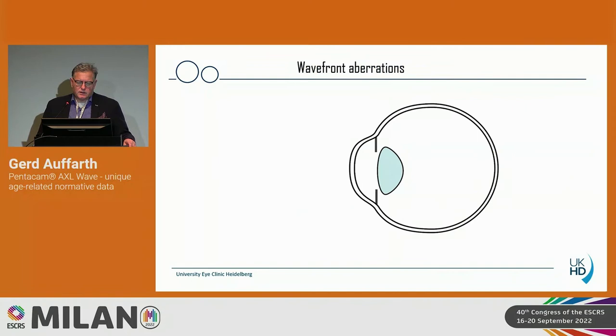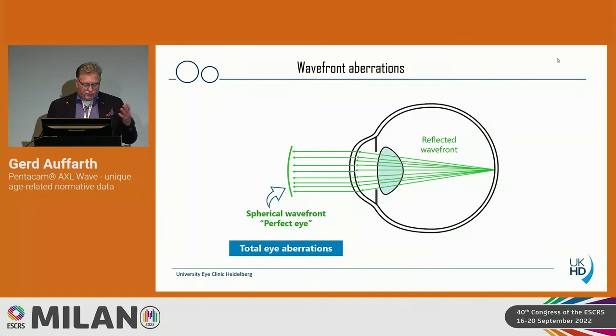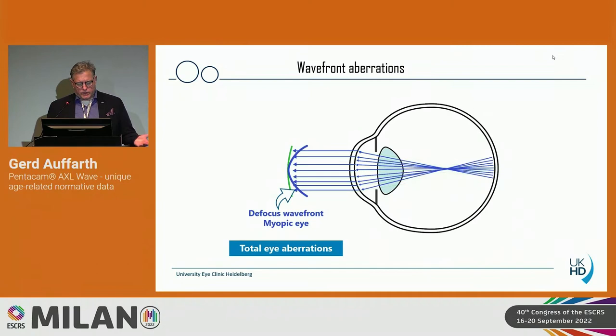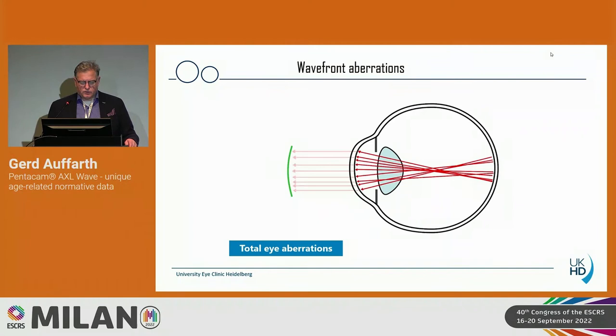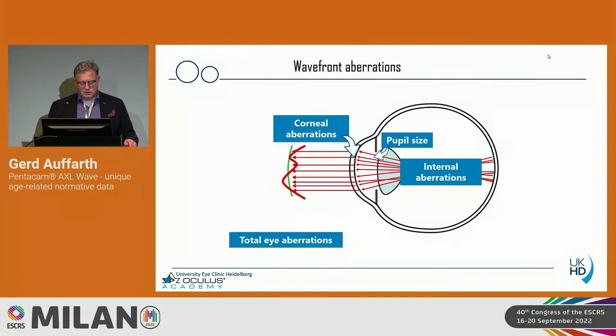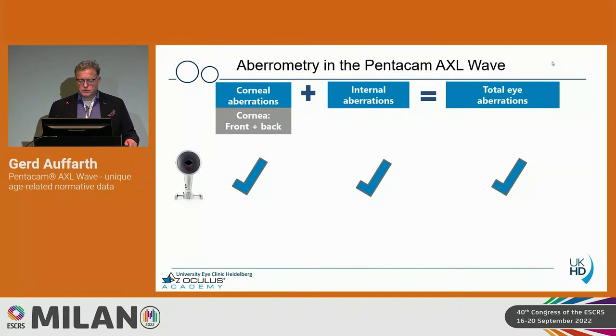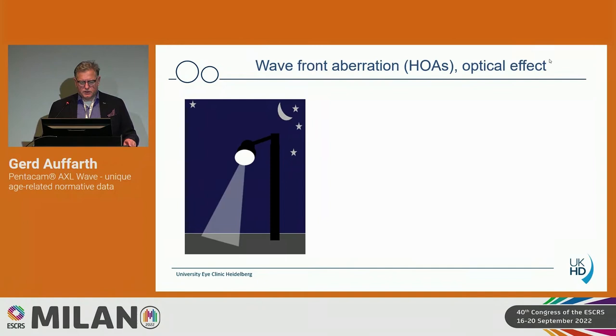Looking at wavefront aberrations: when a beam enters the eye and is reflected back, we assess the spherical wavefront. In a perfect eye we have the total eye aberrations. In a myopic eye, we have a certain defocus. The high order aberrations — the total sum — are built from the corneal aberration, influenced by pupil size and the internal aberration. Corneal aberration consists of front and back surfaces, and they are summarized in the Pentacam AXL Wave measurement of total eye aberrations.